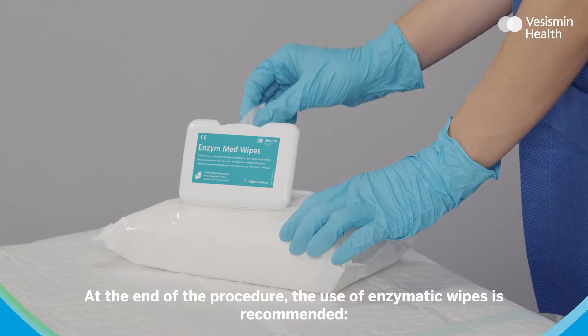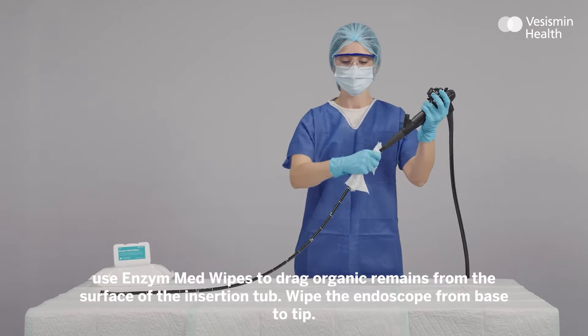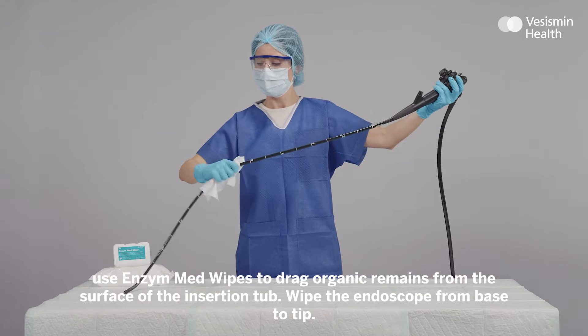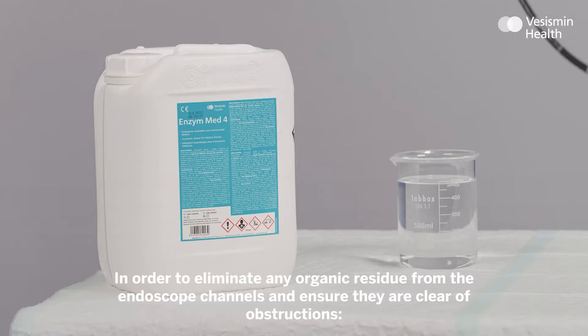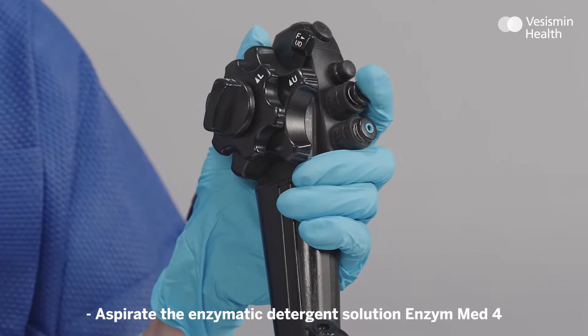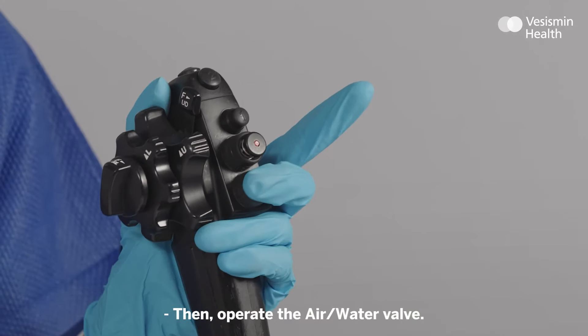At the end of the procedure, the use of enzymatic wipes is recommended. Use Enzym Med wipes to drag organic remains from the surface of the insertion tube, wiping the endoscope from base to tip. To eliminate any organic residue from the endoscope channels and ensure they are clear of obstructions, aspirate the enzymatic detergent solution Enzym Med 4, then operate the air water valve.